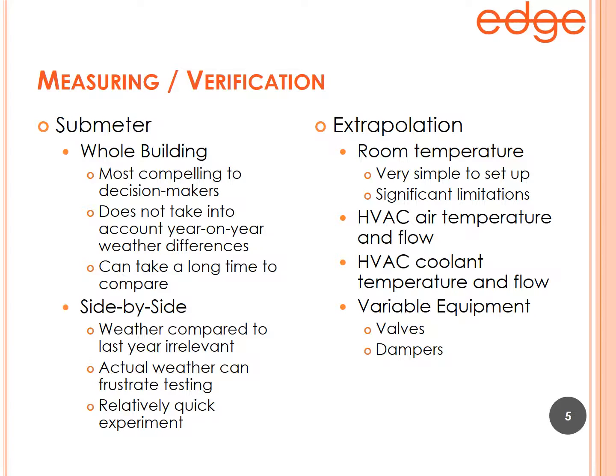For example, in 2015 you sub-meter the cooling system all year, then on January 1st, 2016 you install all the film and measure for another year. But what if 2016 was an extraordinarily hot or cool year, or vice versa? It doesn't account for the fact that year-on-year weather differences can be significant.